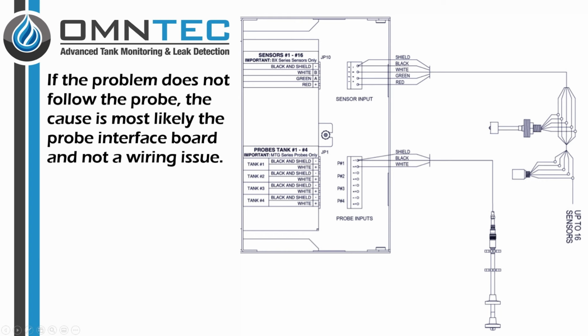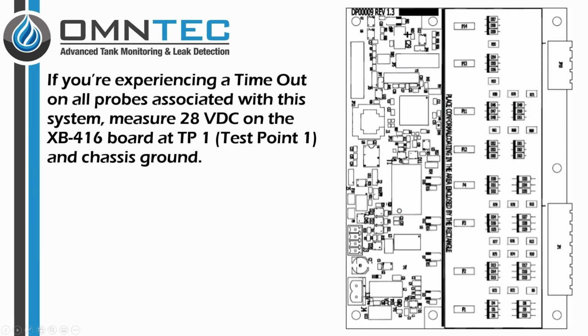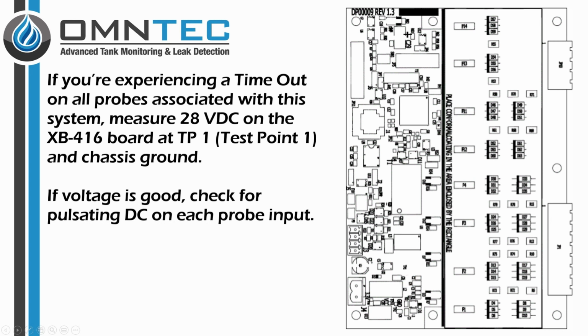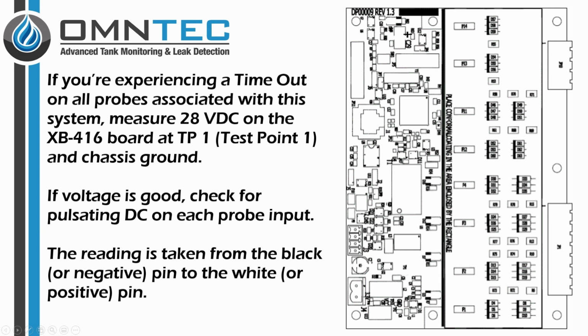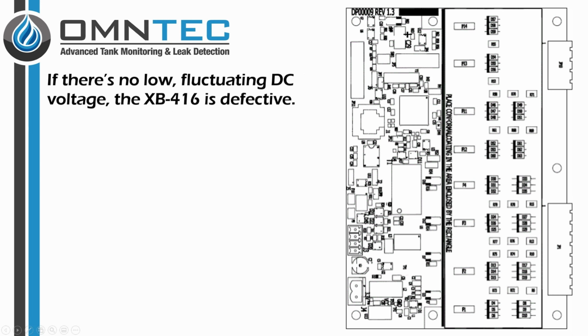If you're experiencing a timeout on all probes associated with this system, measure 28 volts DC on the XB416 board at TP1, or test point 1, and chassis ground. If voltage is good, check for pulsating DC on each probe input. Reading is taken from the black or negative pin to the white or positive pin. If there's no low fluctuating DC voltage, the XB416 is defective.